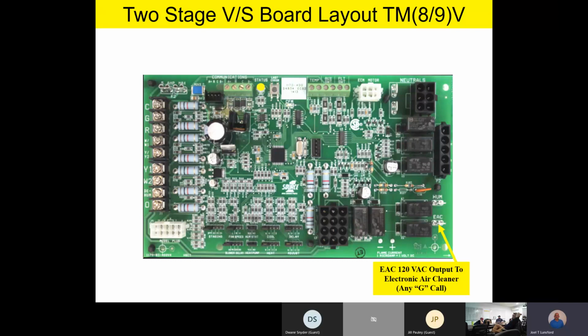Now, please bear in mind, if you're using an electronic air cleaner in this example, that's a 24 volt electronic air cleaner, you're going to make sure and take the 120 volt off of this, and you're going to provide another transformer, a step down transformer. So that's how we normally see this taking place.